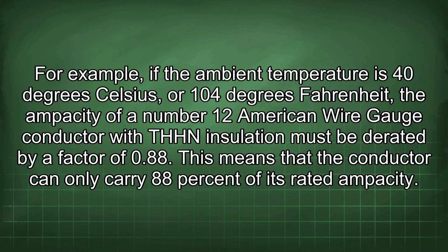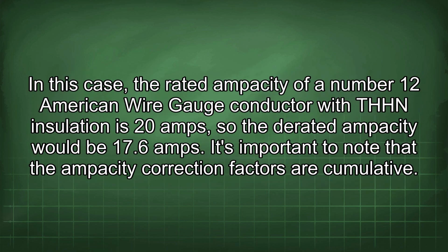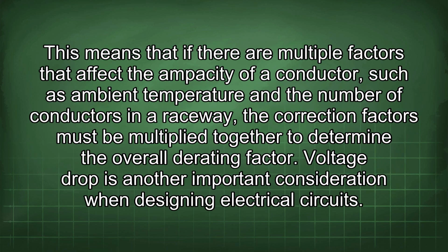This means that the conductor can only carry 88% of its rated ampacity. In this case, the rated ampacity of a number 12 American wire gauge conductor with THHN insulation is 20 amps, so the derated ampacity would be 17.6 amps. It's important to note that the ampacity correction factors are cumulative. This means that if there are multiple factors that affect the ampacity of a conductor, such as ambient temperature and the number of conductors in a raceway, the correction factors must be multiplied together to determine the overall derating factor.